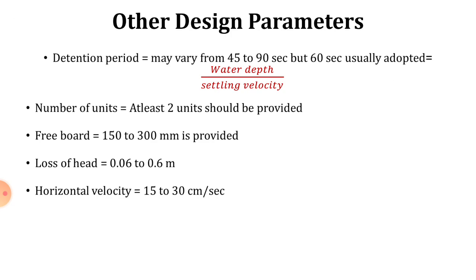Other design parameters include: detention period, which may vary from 45 to 90 seconds but 60 seconds is usually adopted, calculated as water depth divided by settling velocity; number of units — at least 2 units should be provided; freeboard of 150 to 300 mm; loss of head allowed is 0.06 to 0.6 meters; and horizontal velocity should be maintained between 15 to 30 cm/s.